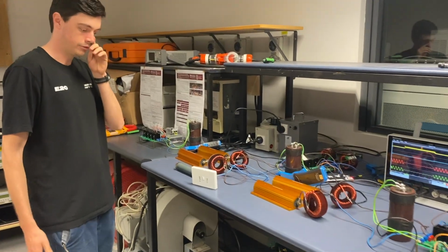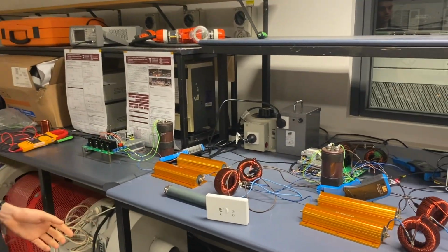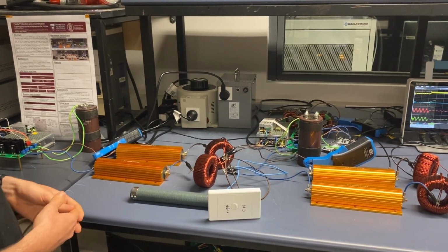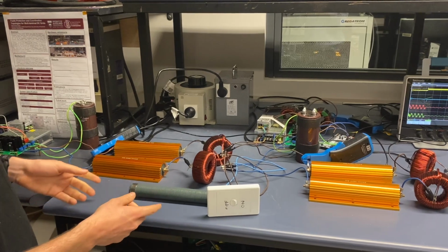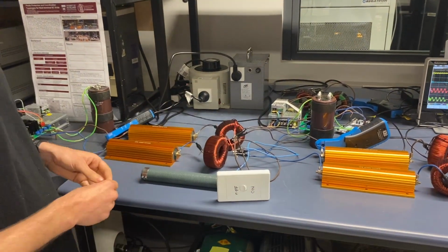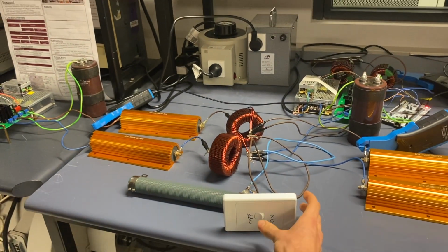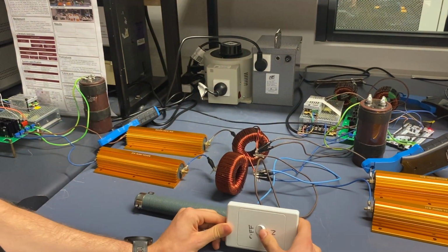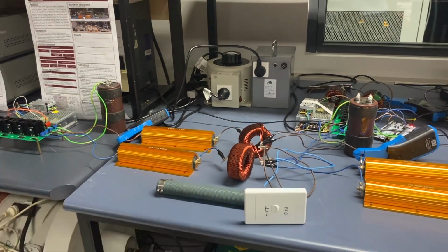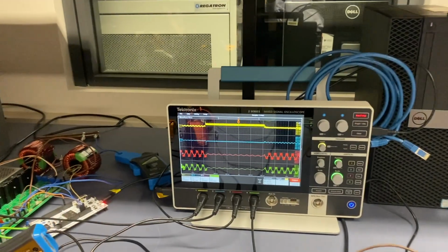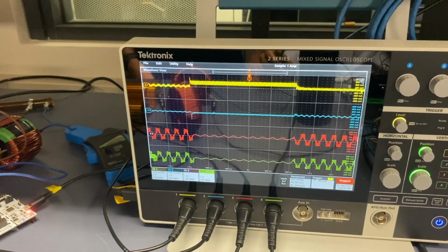So the first fault we're simulating is just before terminal 2, which is in zone 1. We have our fault resistance of 1.5 ohms connected across here. This is a pole-to-pole fault, and we can simulate this fault by flipping the switch to short through the resistor, and then we are measuring it on the oscilloscope, as David said before.